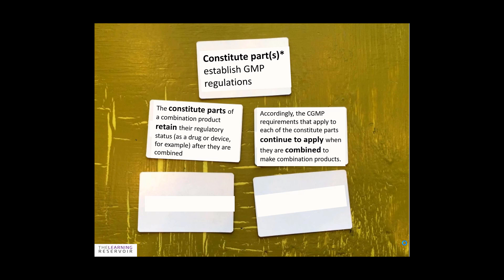For example, in a drug-eluting stent, the drug and the stent come together to form a drug-eluting stent. Our constituent parts in this case are our drug and our medical device or stent. Accordingly, the CGMP requirements for a medical device must be adhered to, and for a drug must be adhered to, when you're manufacturing a drug-eluting stent in a facility. So you must implement the rules for both drug CGMPs and medical device GMPs.